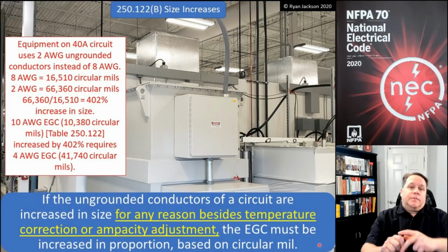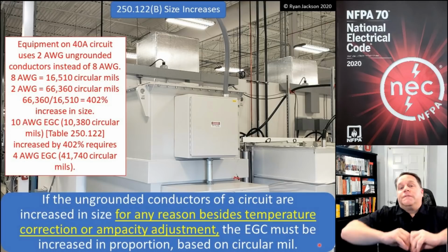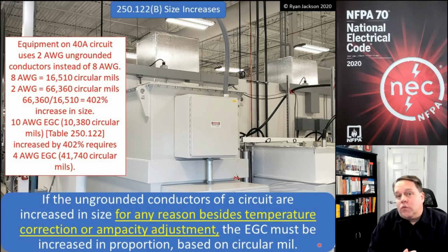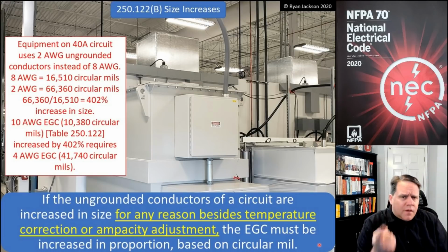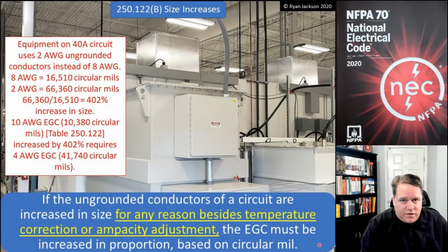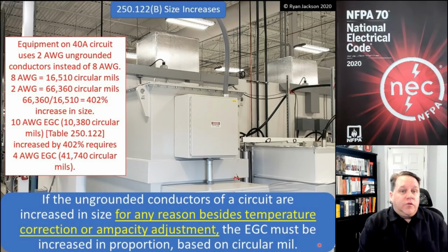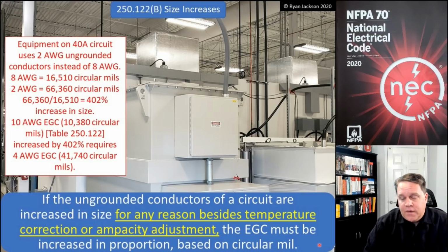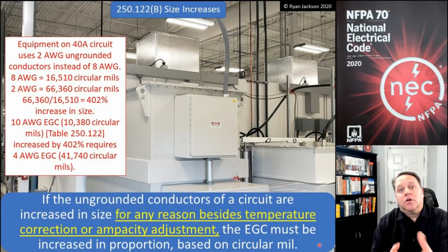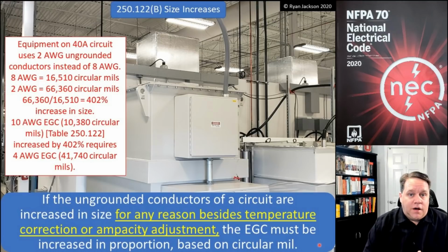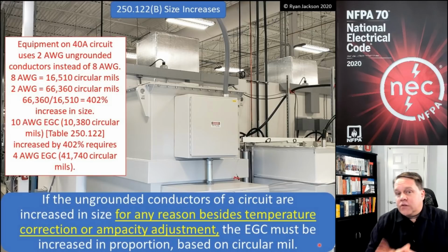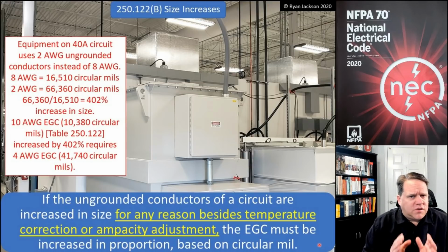What they ended up doing is they completely started over in all of 250.122. The whole fundamental concept of how we size equipment grounding conductors, they were going to revisit. So they said, you know what? Forget it. We are never going to size it off the breaker or fuse. That's not what we're going to do anymore. We're going to size the equipment ground based on the size of the ungrounded conductors that it's associated with. And they voted on it and they passed, and that was what was going to be in the code. They published that in what we call the first draft of the NEC, and that's where it's open for public review. And you can submit comments on the code changes. You can say, look, that's a good idea, keep doing it, or that's a bad idea, you should have done this or that. Well, a lot of people read what they did and lost their mind, myself included. And a lot of people submitted public comments saying, hang on. If we want to solve 250.122(B), let's solve 250.122(B). Let's not reinvent the entire scheme of grounding and bonding in the NEC. So the code change process worked exactly like it's supposed to.